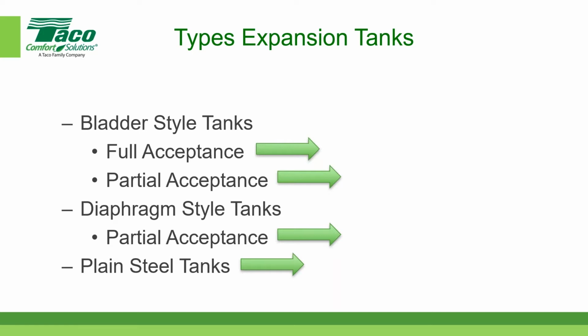One of the important distinctions between the top two, bladder and diaphragm, versus plain steel, is that in the top ones there's a definite separation between the water and the tank itself, with an air cushion in between. In a plain steel tank, the system water is actually just in that tank. That's one of the big distinctions - the diaphragm or the bladder captures that water.